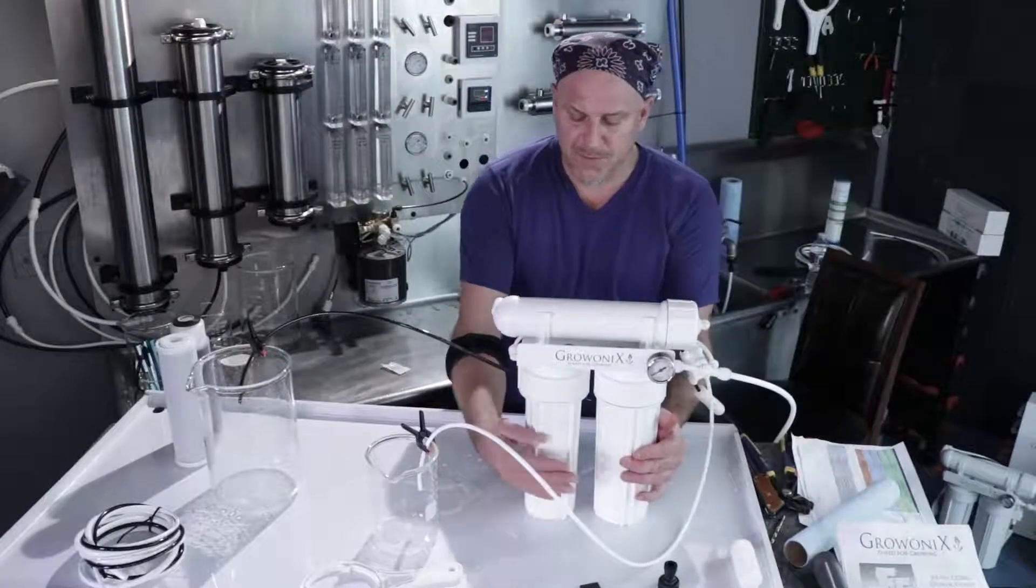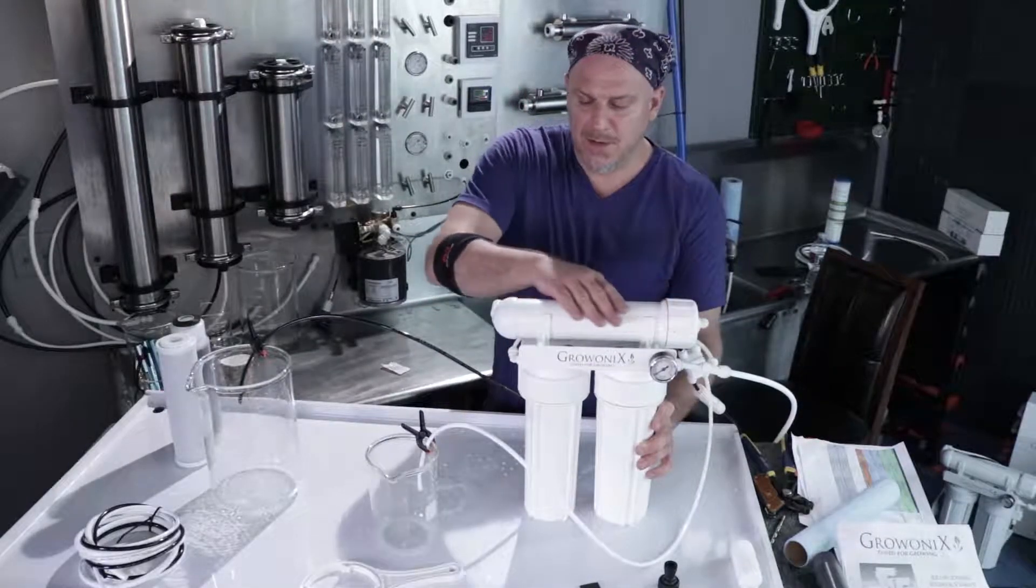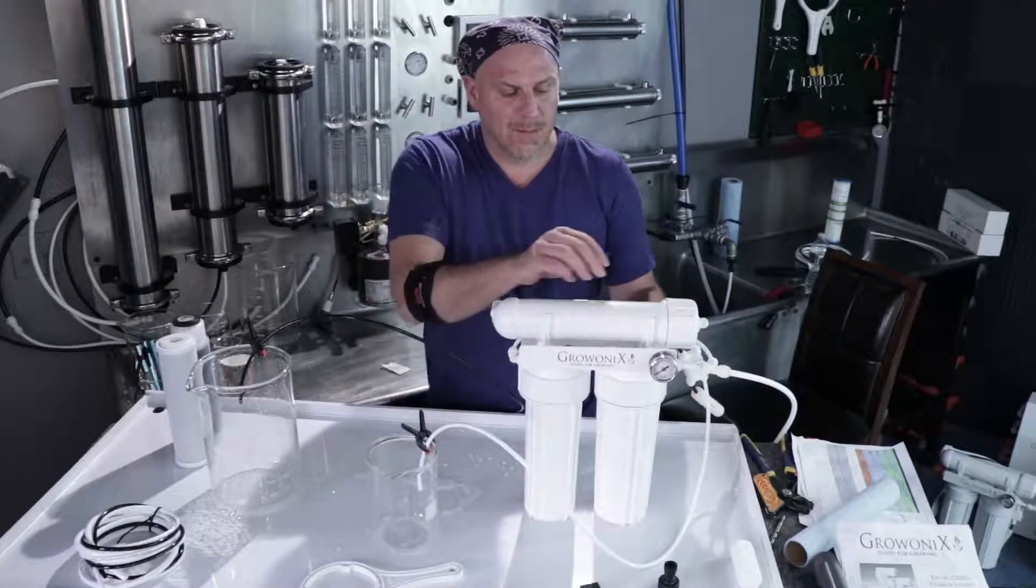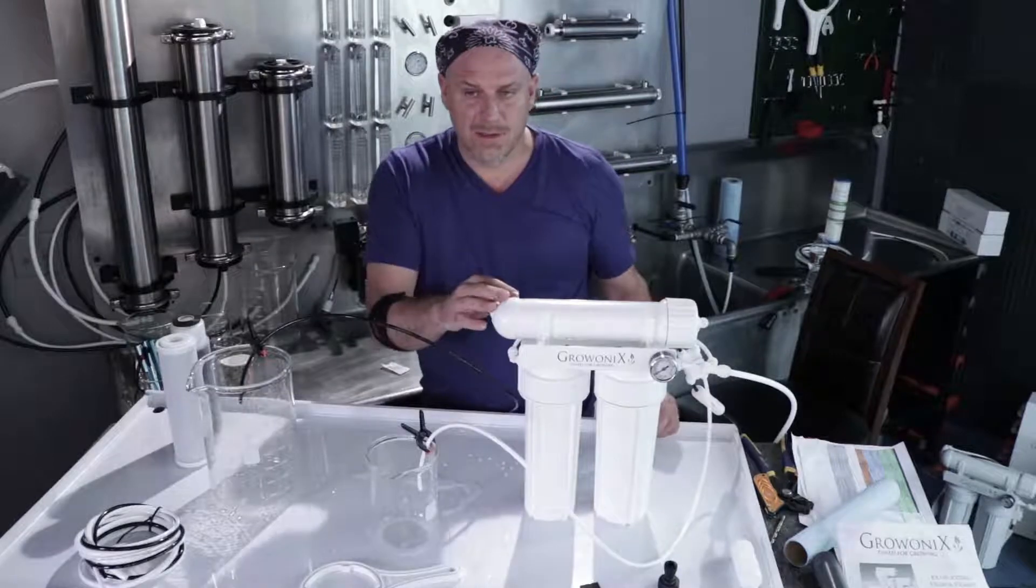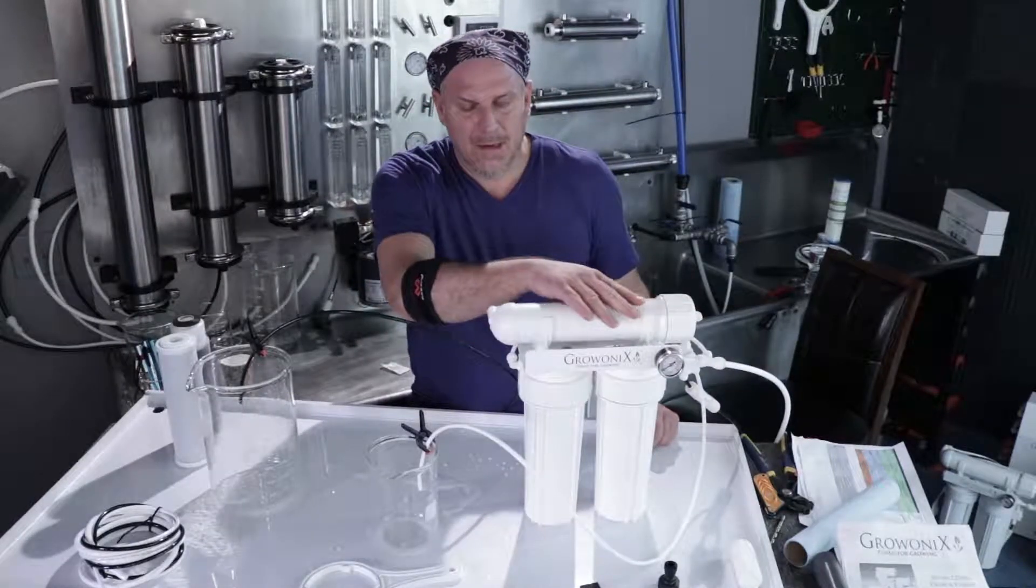So we flushed the pre-filters, the carbon's been flushed, now the water is going to enter the membrane to flow this way and then out to the drain kit. The membrane through manufacturing has a storage solution in it, it's a dry food grade glycerin and we want to flush it out.